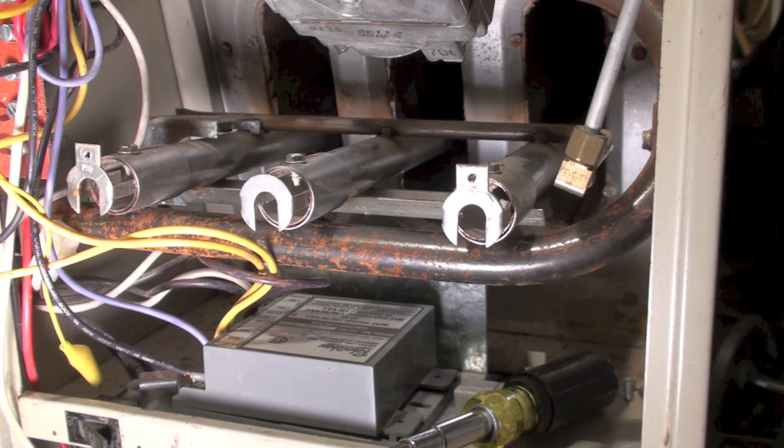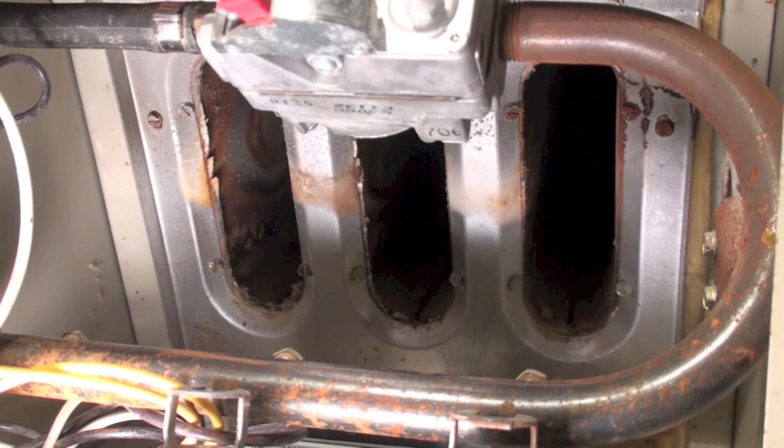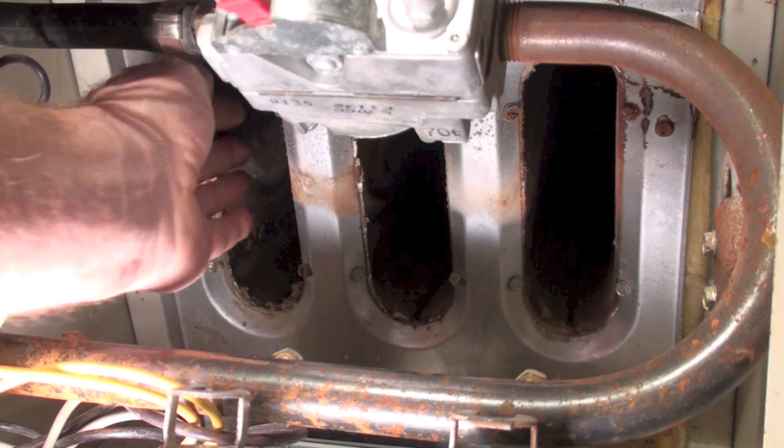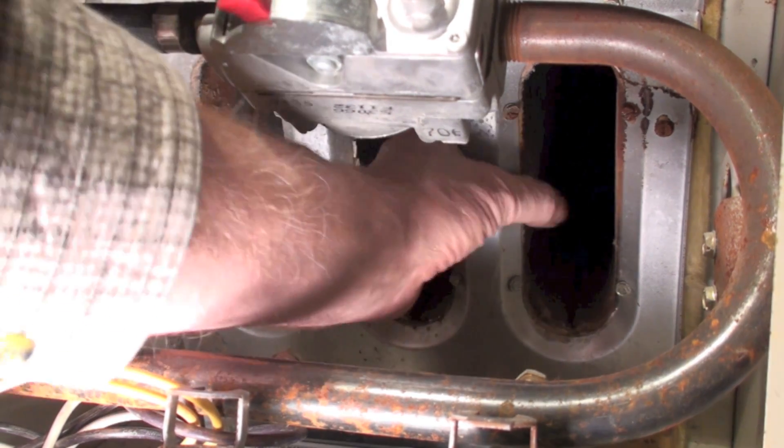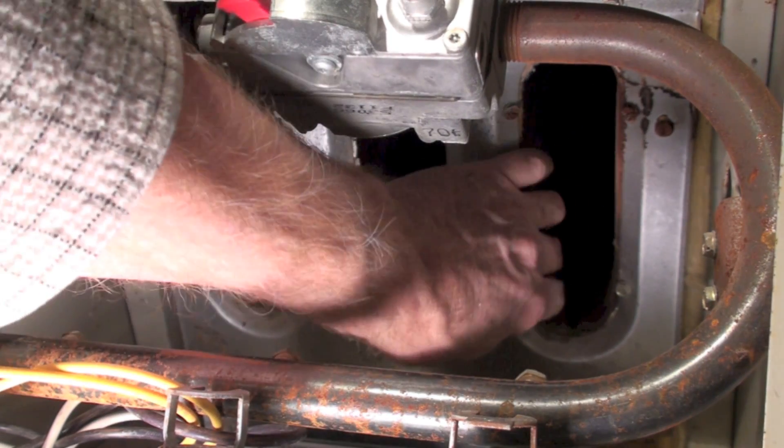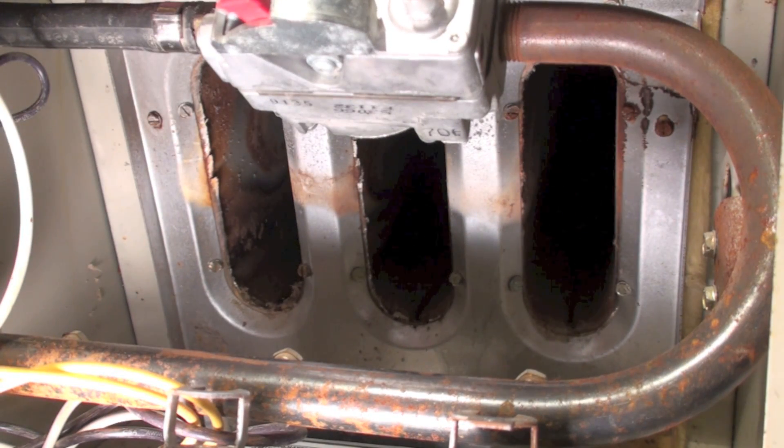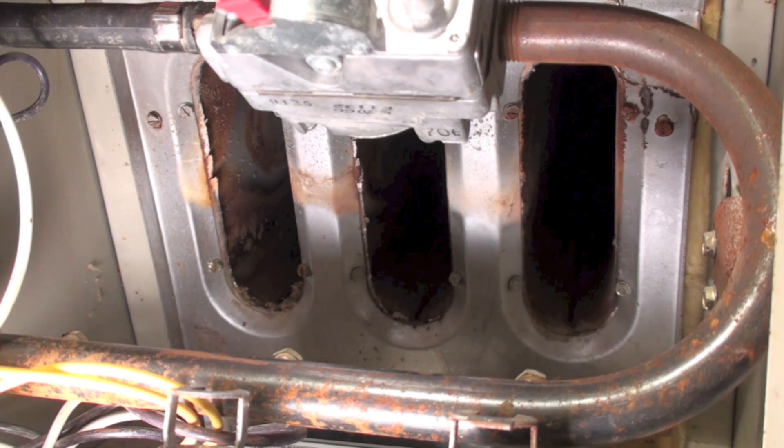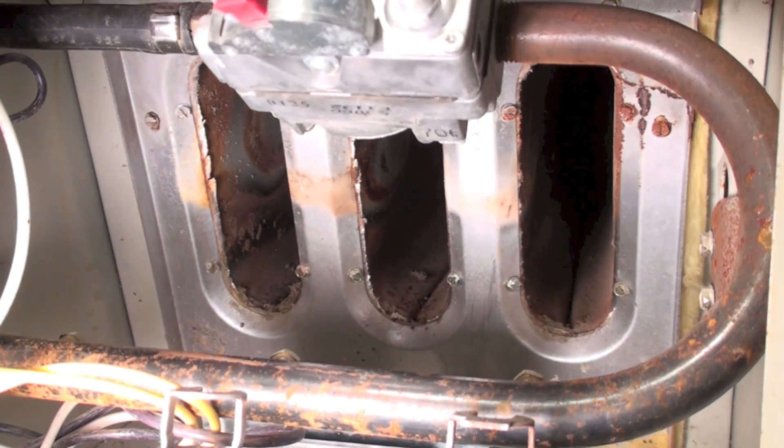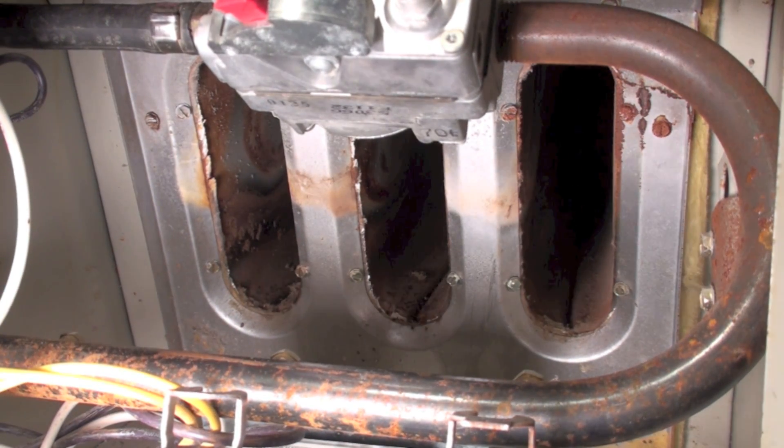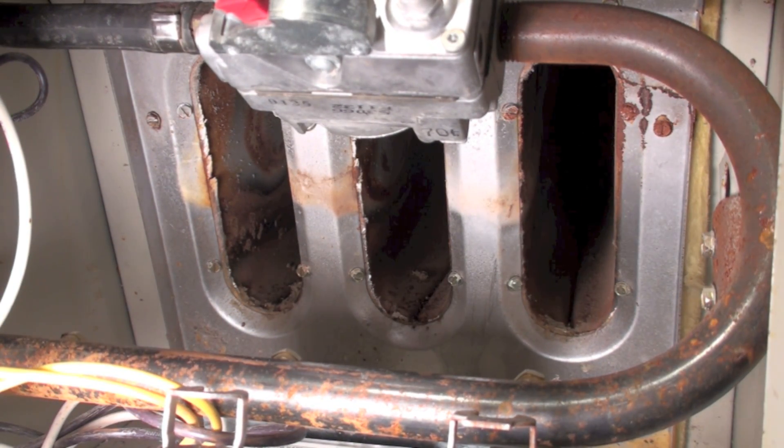And you can see those slots there, just slide right out. While these burners are out, this is a time when you should be looking in the heat exchanger using your flashlight up in here, making sure it's not rusted out or doesn't have any cracks in it. This is where a camera is really nice. It's not absolutely necessary, but it's certainly nice to have something like that in there where you can snake that thing in there and make sure you catch every place.